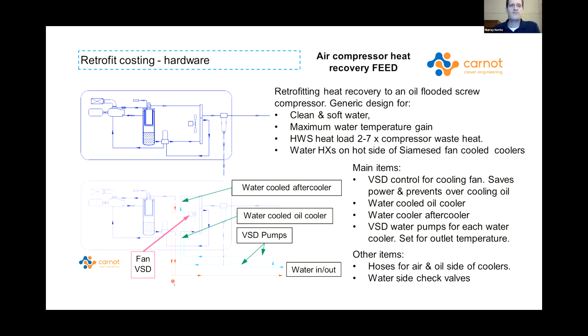We've heard from Jensen about the need to have split systems. We've got variable heat loads in the oil cooler and the after cooler. So run variable speed pumps that are controlled on the temperature coming out of those coolers. So you give the heat recovery system the first grab at the water. You run nice slow water flows through it, so you get maximum temperature rise. The pumps, you tell them what temperature you want to come out and they run at that speed to give you that water. If you're getting too greedy and going too high, well, the fan will run, you'll get your hot water, but maybe not all of the heat.